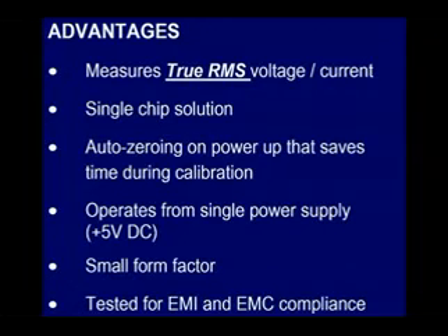Why Cypress solution for the digital panel meter? First of all, this solution that we have measures true RMS, voltage and current. It's a single chip solution. It does auto zeroing on power up that saves 1 point for calibration. It operates from a single plus 5 volt DC supply. We do not need any dual supply voltages in the system. It's a very small form factor, very low component count, and it has been tested for EMI and EMC compliance.